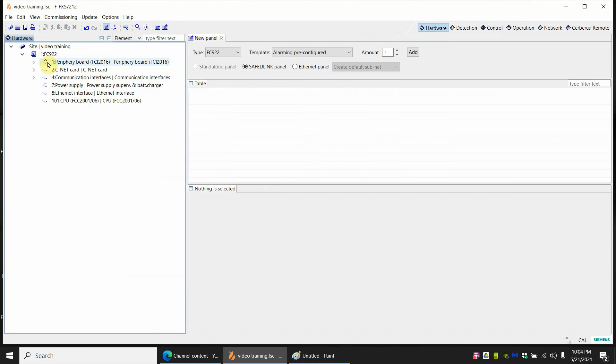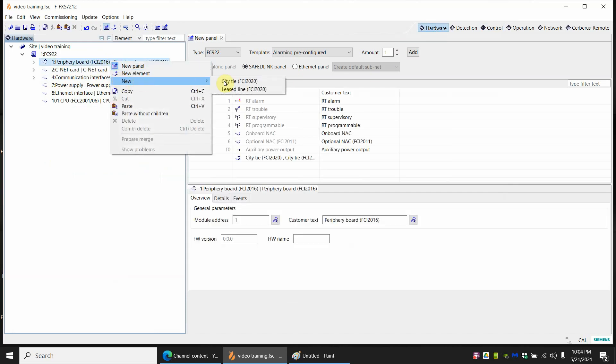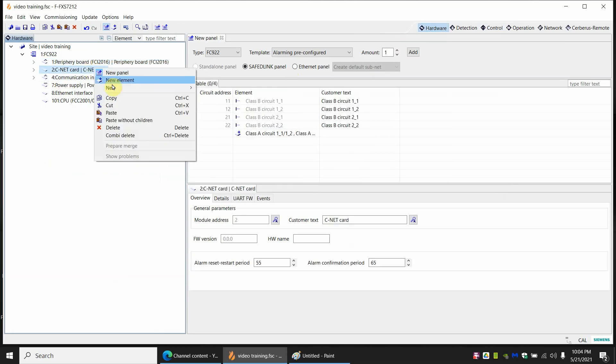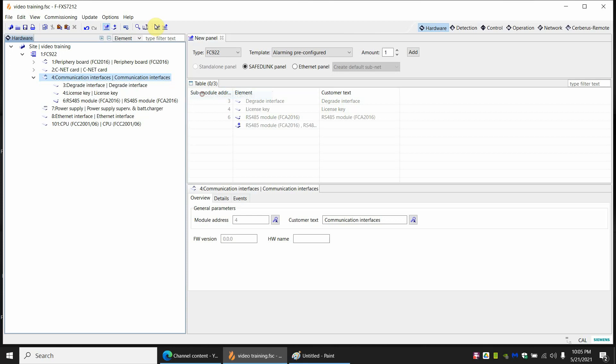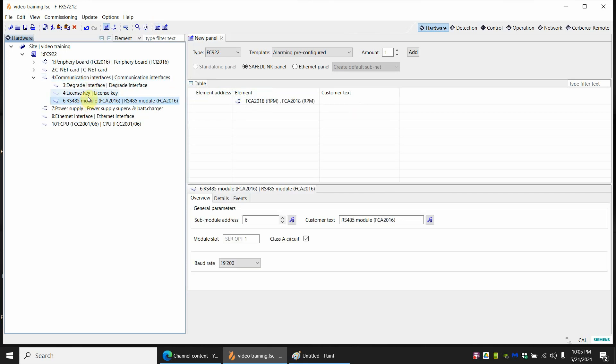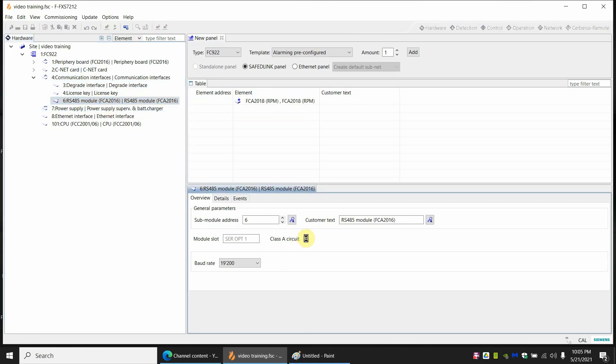The next thing we're going to add is we're going to add a remote terminal or a remote annunciator if you will. Now if you're not sure where to add this you can feel free to click on each one of the NACs and hit new and see what shows up. Well not there. We're looking to add a RS-485. Does it go on the CNET card? No. Does it go on communications? New. There's an RS-485. So we add that in and it adds it right here. Now by default the system will add the RS-485 as a class A circuit. If you do not wish to use class A which I rarely do for most systems there is a checkbox here. You can uncheck it and now it's class B.